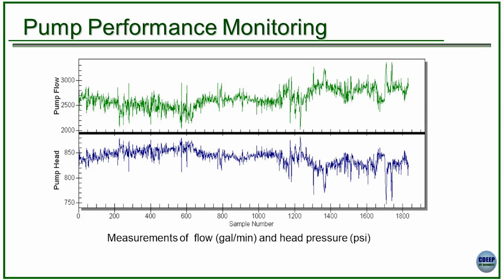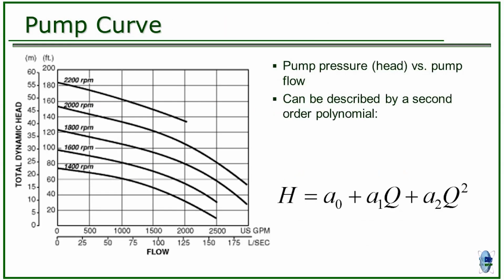We know that a pump operates on a specific characteristic curve. Depending on the head required and the flow required, you can operate the pump at a specific revolution per minute, so the pump would lie on one of these lines. It's easy to obtain a model of this, a simple quadratic curve that you can fit.